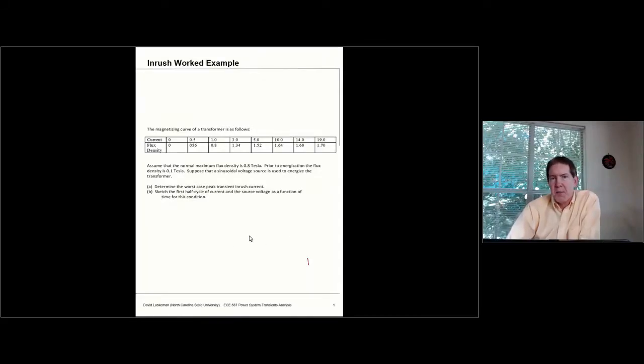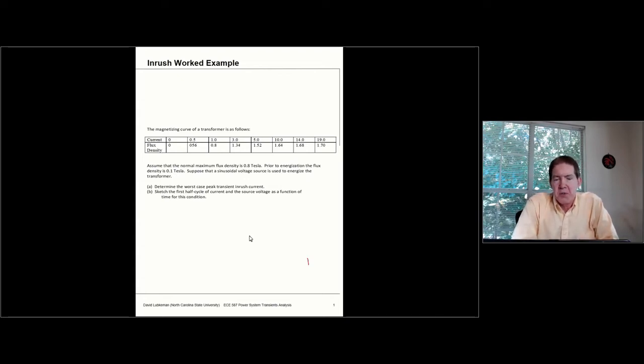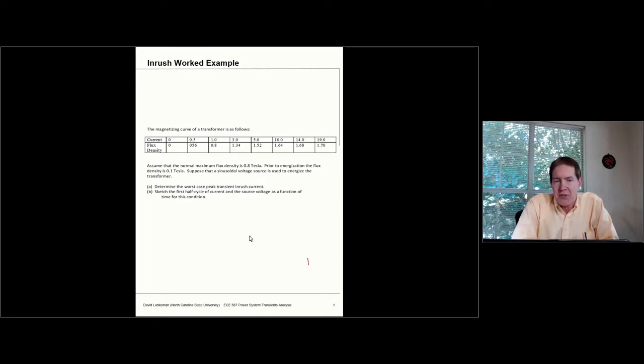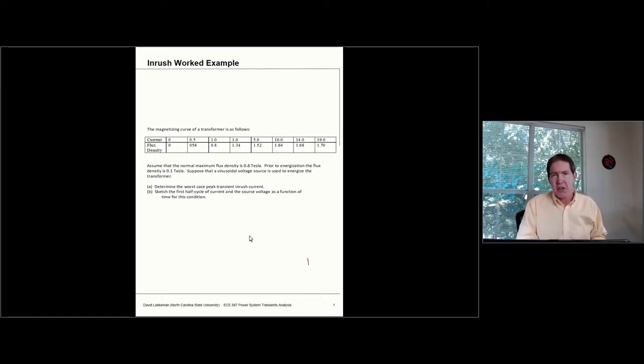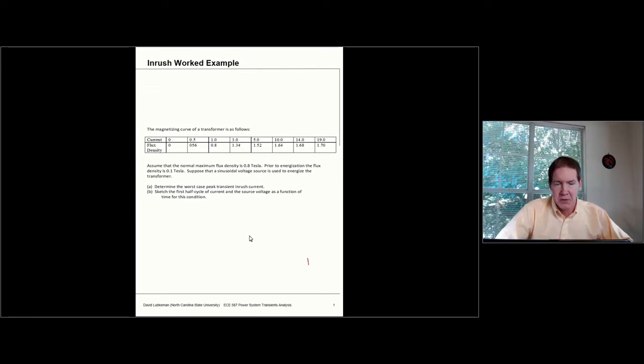Let's take a look at a worked example focusing on inrush. In this particular case, I've got a situation where I'm energizing a transformer with the characteristics as shown. Instead of having a BH curve, I have a BI curve — a flux density versus current relationship. You'll do something similar for your homework, but with a different format for the data.